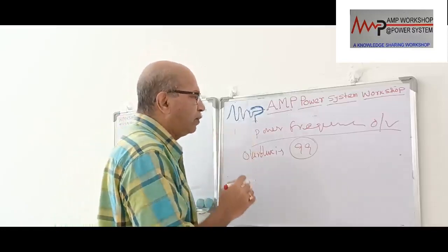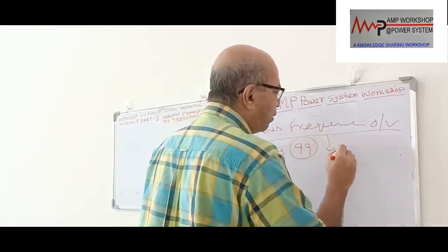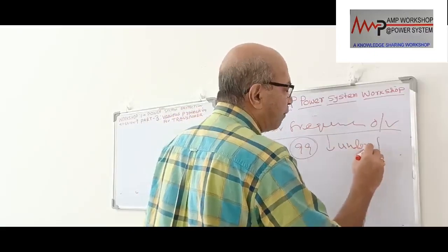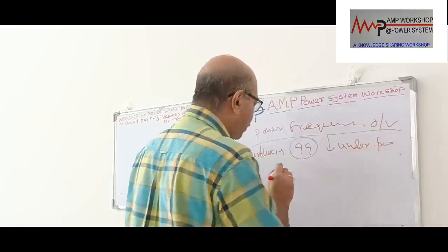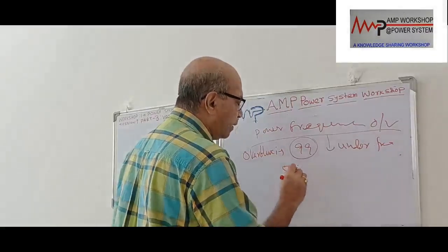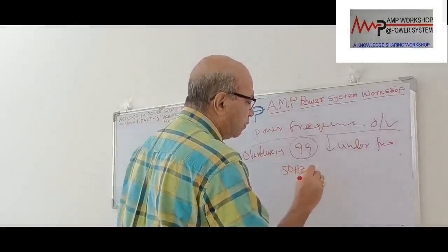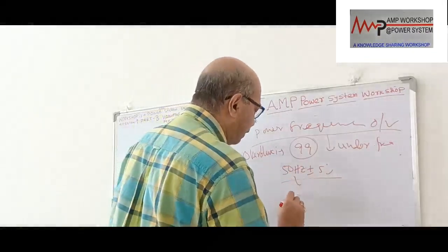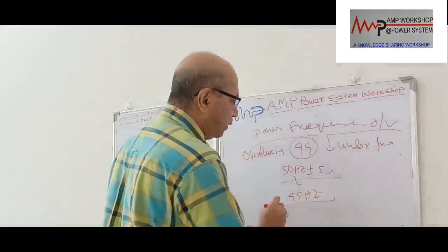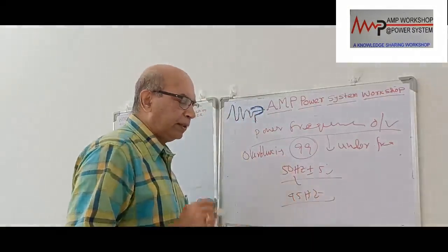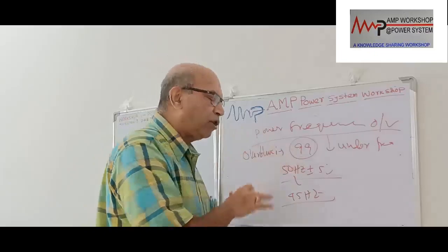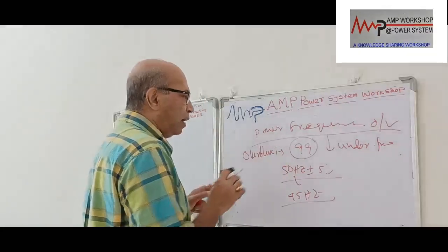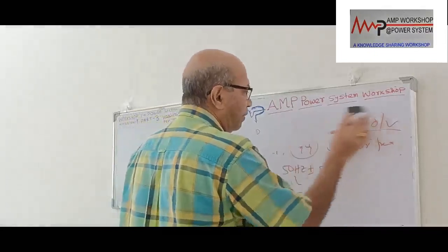And along with this, there is under-frequency operation. The voltage coming to the transformer, if it is under frequency, normally its frequency is 50 hertz, 50 hertz plus or minus 5% we allow. Now if this frequency comes to 45 hertz, lower than the rated condition, then this overvoltage along with the low frequency is very severe. Why is low frequency severe? That we'll discuss now in brief.